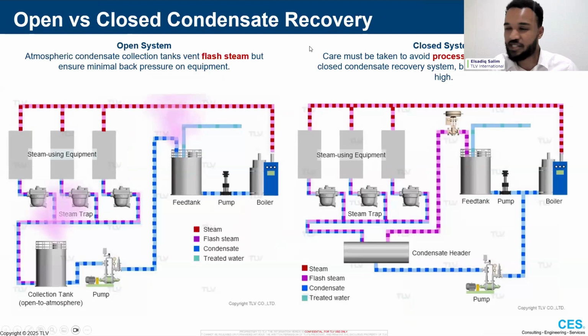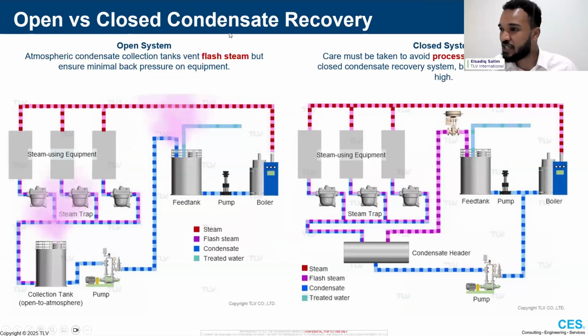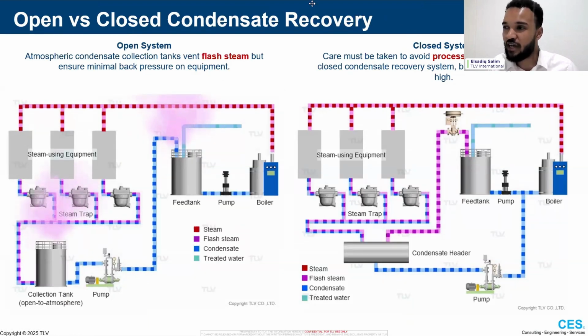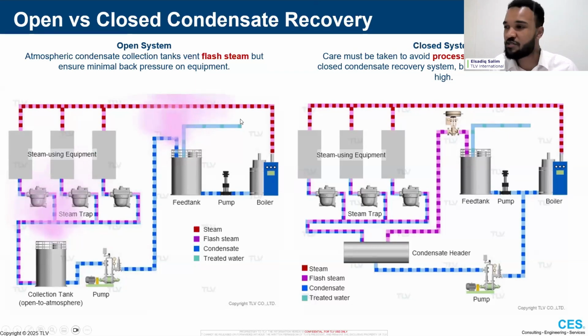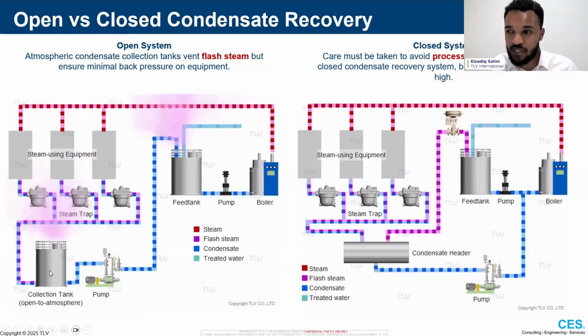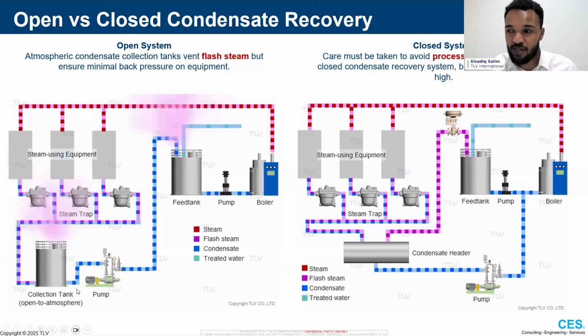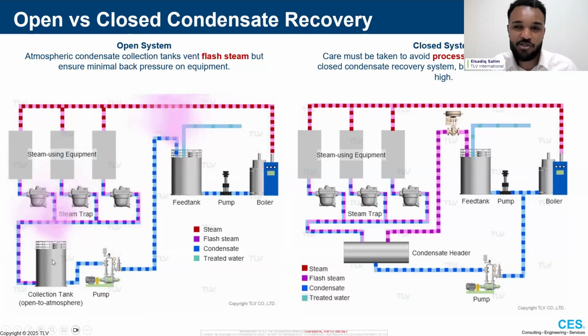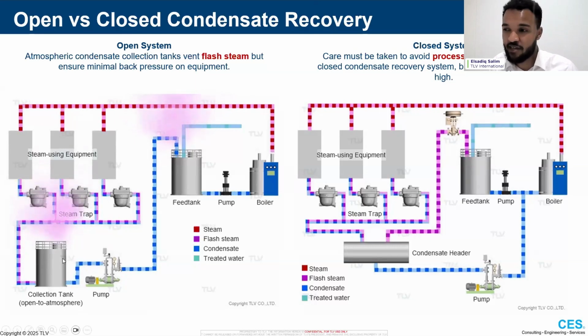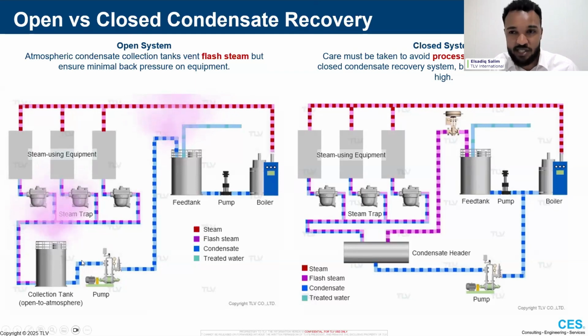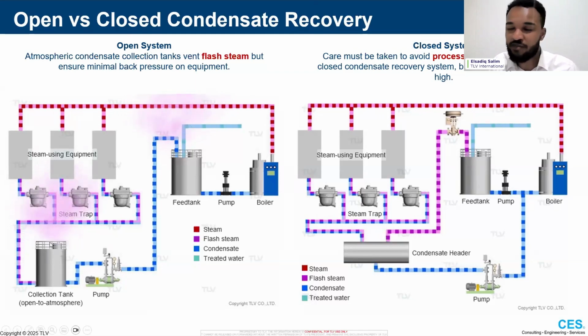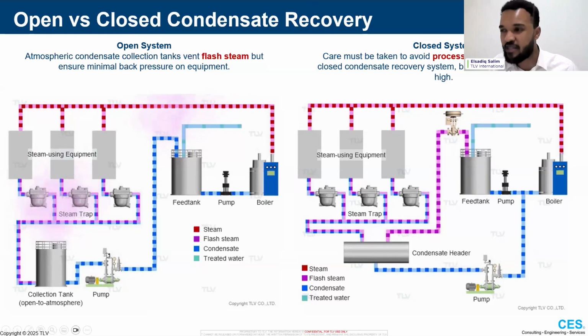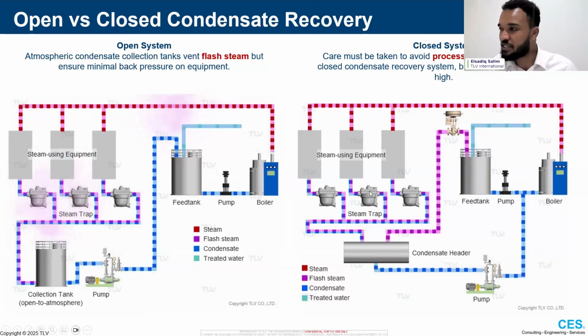It's all well and good talking about condensate return like it's the easiest thing to do. But I want to talk as well about some of the challenges with that. So typically, condensate return, we look at open systems or closed systems. Today, we'll be talking about open systems, which is where a site might have condensate collection tanks strategically placed around their site, where the steam traps can discharge into, and then there'll be an open vent to make sure there's no back pressure. And then that'll get pumped back into the boiler system.